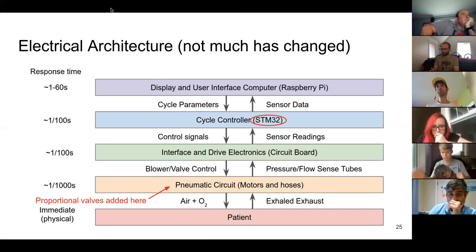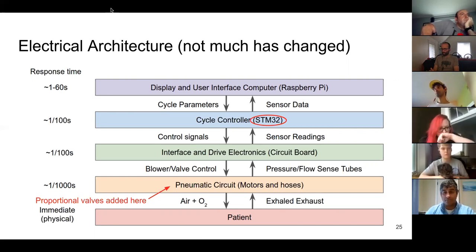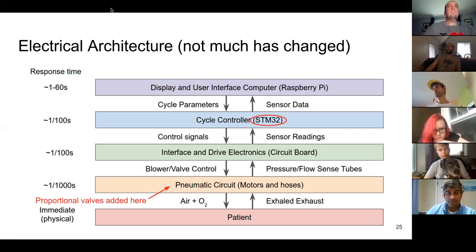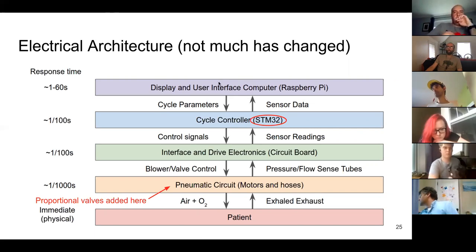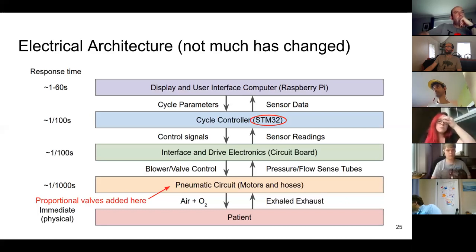So we don't have to worry about what the UI might be doing in the background, which might change the response time of the pressure control loop. The other reason is that there's a significant separation in the response time of each of these systems. Up at the top you see the user interface response time, which is the response time of a clinician or caretaker interacting with the unit and updating it for the patient's condition, all the way down to the patient's actual physical response, lungs inflating and deflating, which is physics.